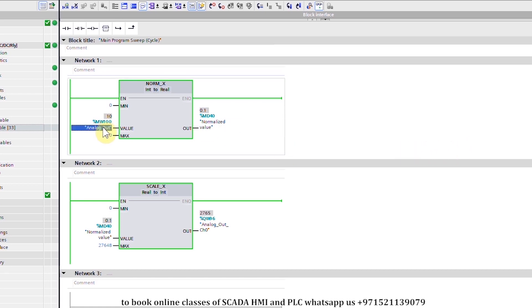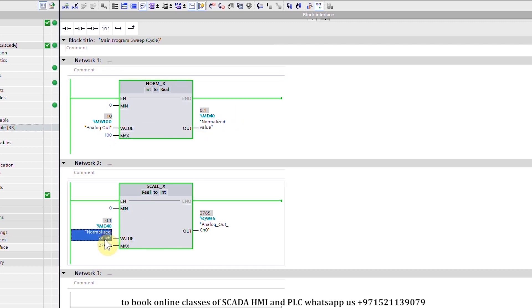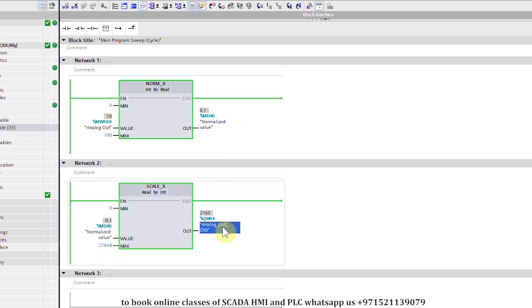We have entered 10 in Memory Word 100. The normalized value is 0.1, and it is being scaled between 0 to 27648. The result is 2765, and this value 2765 is saved into our output data register. Channel 0 will generate the analog output corresponding to this value in the QW96 data register.